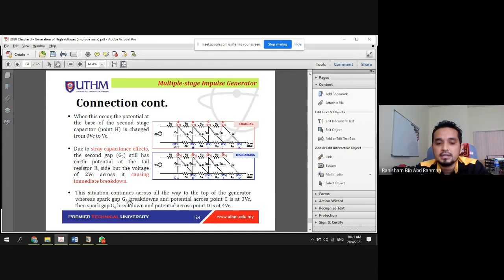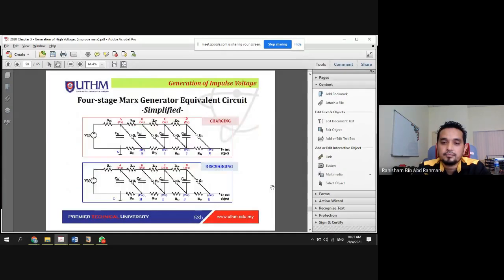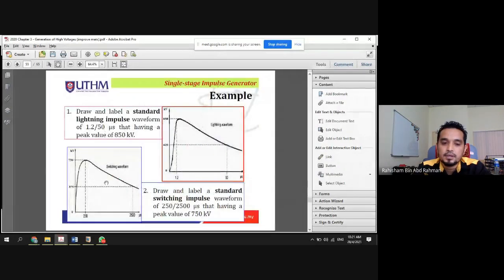This will lead to the breakdown of all stages, which will lead to the final waveform of either switching or lightning type, giving us this kind of waveform but at a different magnitude value. If we use a single stage, not the multi-stage generator, we might just produce 100 kV. But in this case, we are using a 4-stage impulse generator in which each stage is able to generate 100 kV.